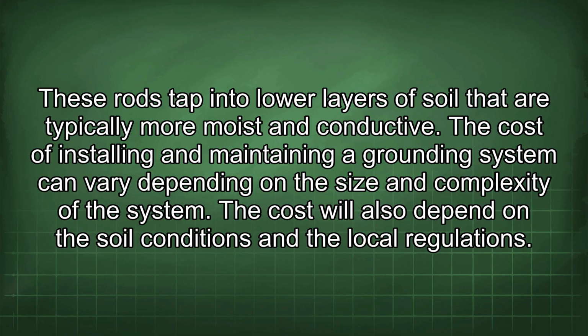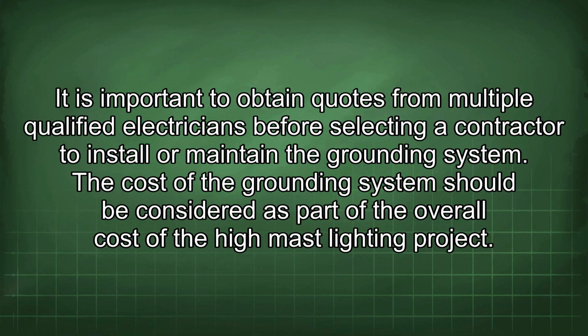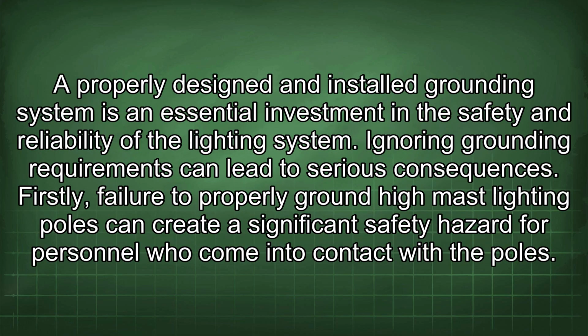The costs of installing and maintaining a grounding system can vary depending on the size and complexity of the system. The costs will also depend on the soil conditions and the local regulations. It is important to obtain quotes from multiple qualified electricians before selecting a contractor to install or maintain the grounding system. The cost of the grounding system should be considered as part of the overall cost of the high-mast lighting project. A properly designed and installed grounding system is an essential investment in the safety and reliability of the lighting system. Ignoring grounding requirements can lead to serious consequences.